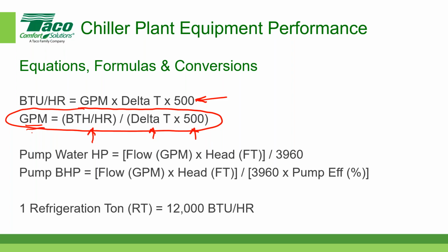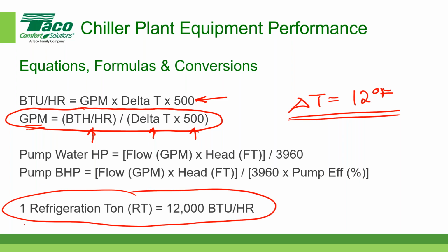So it turns out that one of the things we're interested in knowing is if our delta T, I'll make a diagram here, a triangle, delta T, happens to be equal to 12 degrees Fahrenheit. If we have 1 ton of refrigeration at a 12-degree delta T, and we plug it into this formula up here at 12,000 BTUs per hour, we get 2 GPM per ton. And that's kind of a useful, easy number to remember.